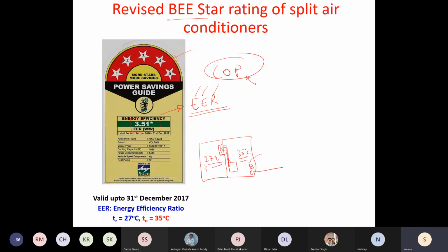And then you will have various probes to check what are the conditions of refrigerant at various points in your AC. Based on that, you evaluate the enthalpy difference across your indoor segment and what is the power consumed by your compressor, and you have to arrive at two important things. What is the cooling capacity? Even if the salesman says it is 1.5 R ton, you still have to look at this number.